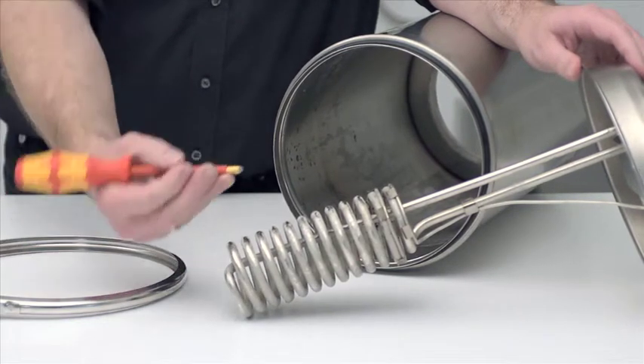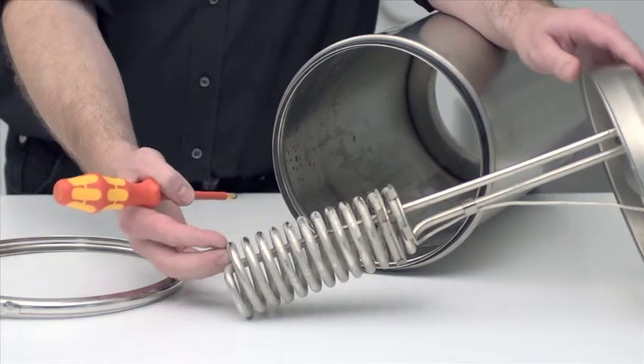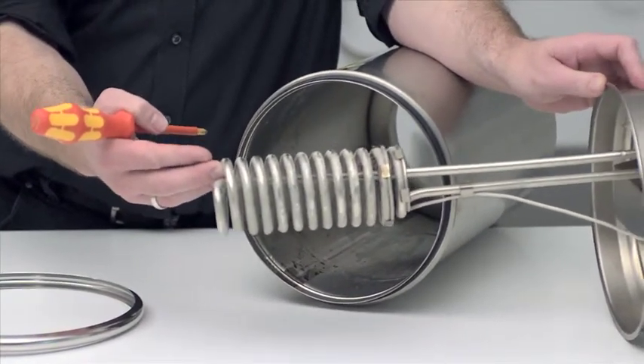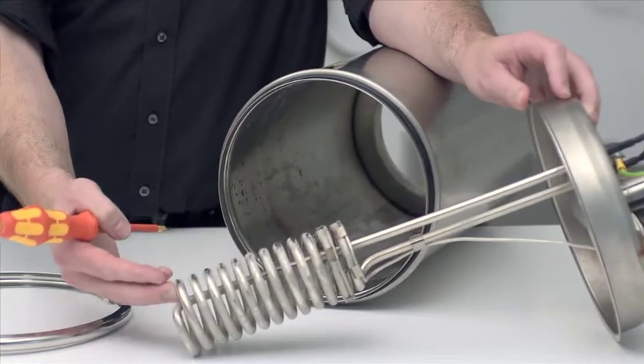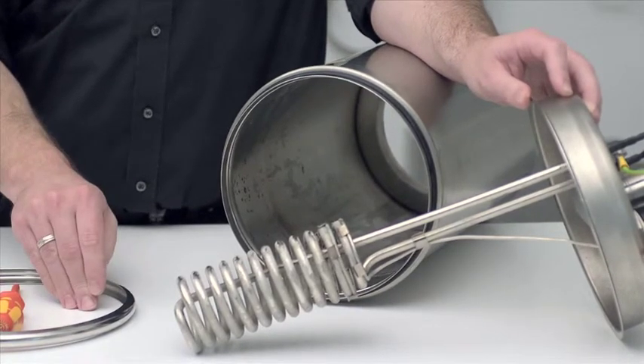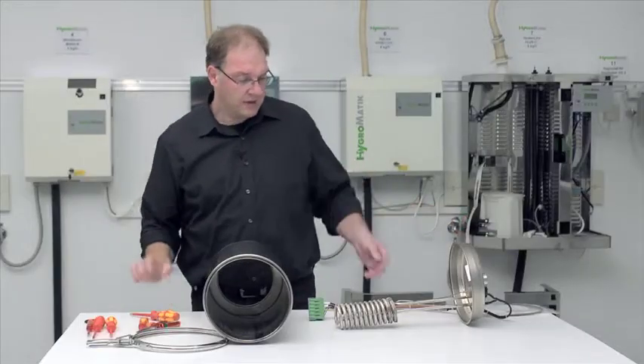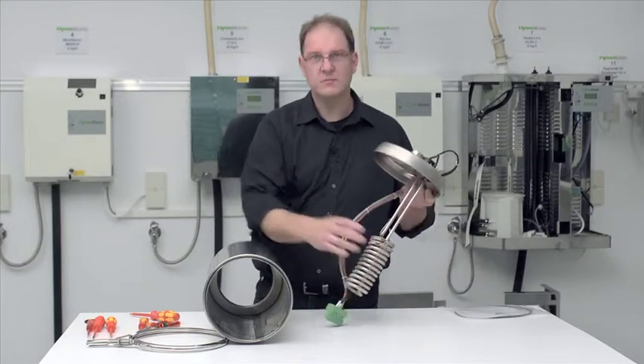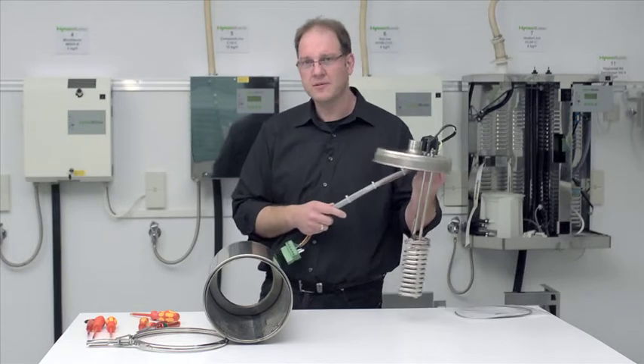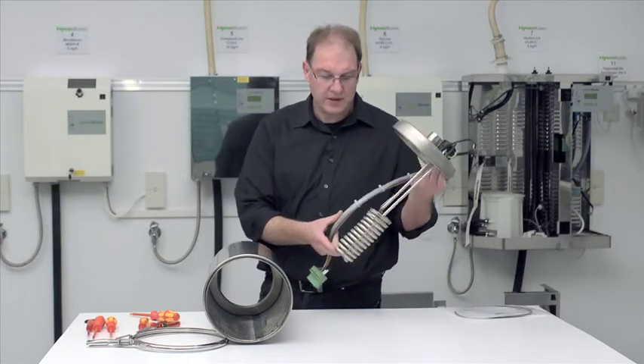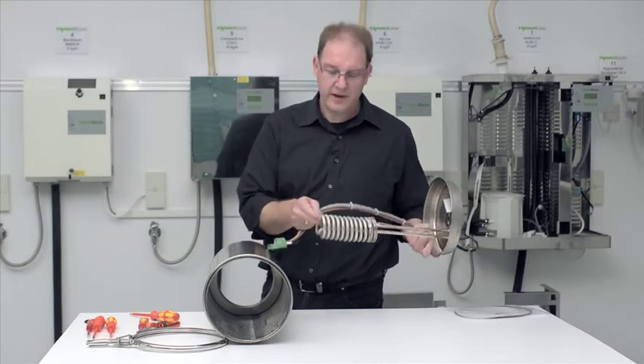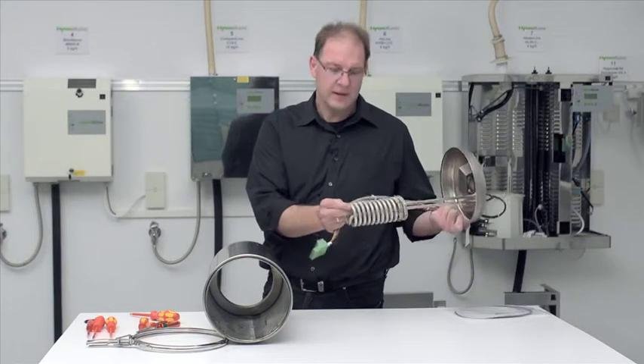When dealing with larger amounts of calcium deposits which you might not be able to remove mechanically we recommend placing the whole thing in a cleaning bath. Normally the cleaning agents have a certain acid content. Please make sure the acid content of the cleaning bath does not exceed 10%. You can see how the calcium deposits dissolve and when the heater elements are free of scale again, especially the areas between the coils, then just take it back out.